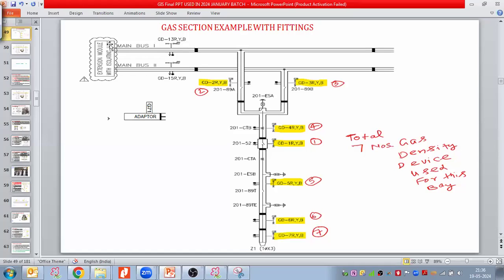So when you review the gas SLD, and if there is a probability of future extension of the substation, then keep in mind that at the end of the bus bar where the future extension is to be proposed, at that side of the bus bar, take the end module or take the extension module with isolating link.